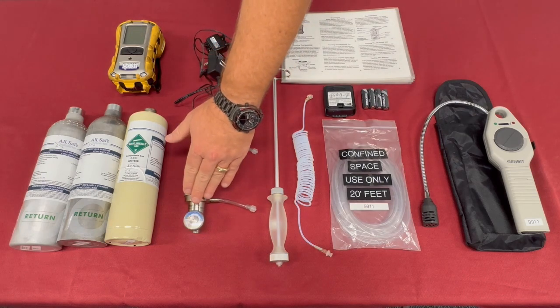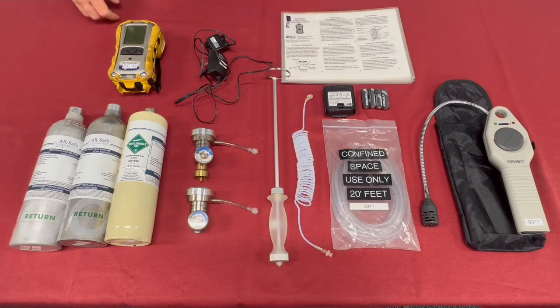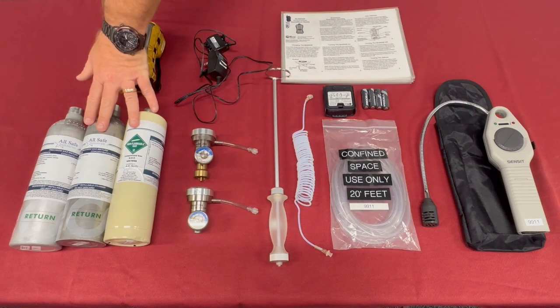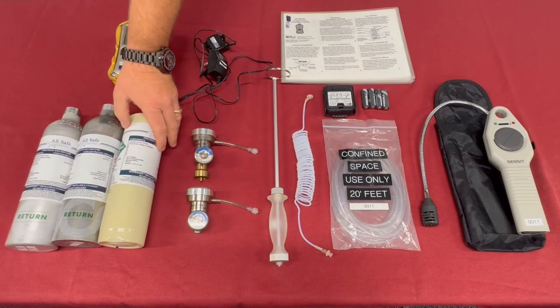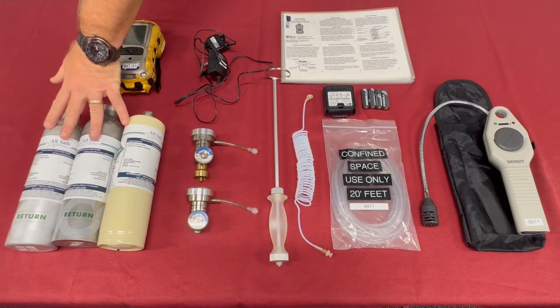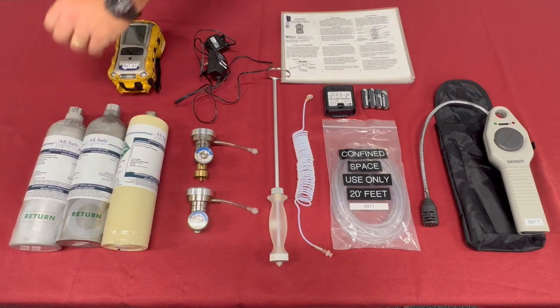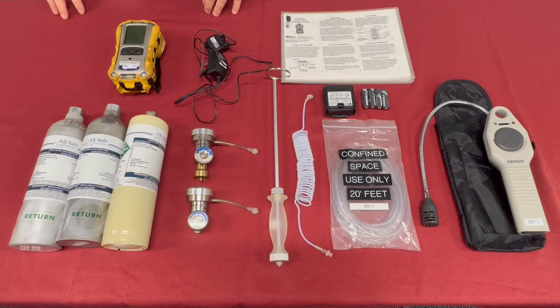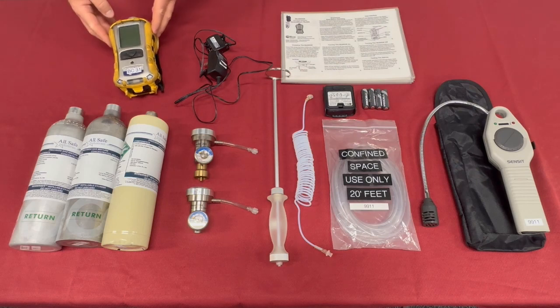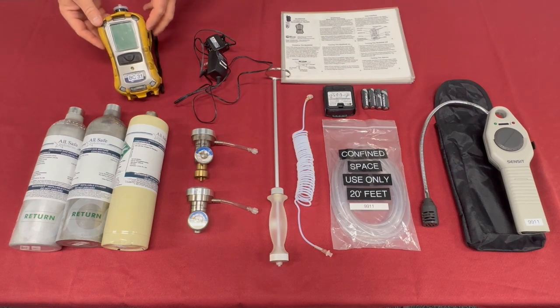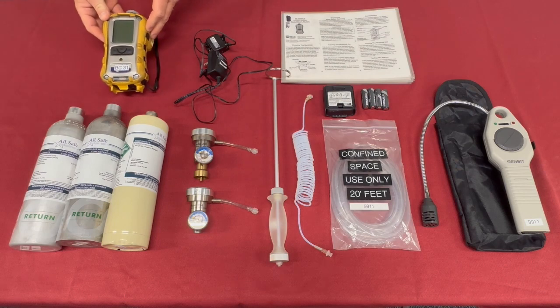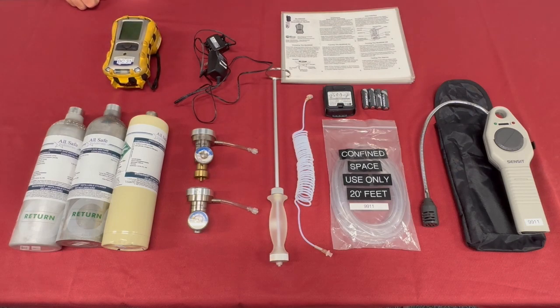We have 2 different types of demand flow regulators for use with our 3 calibration gases. We use 3 separate calibration gases that we'll go into in detail when we do the actual calibration of the meter. And finally, the RAE Systems MultiRAE Lite meter. This is what's carried on all of our companies, so we'll go into how to calibrate it and proper usage here in just a moment.